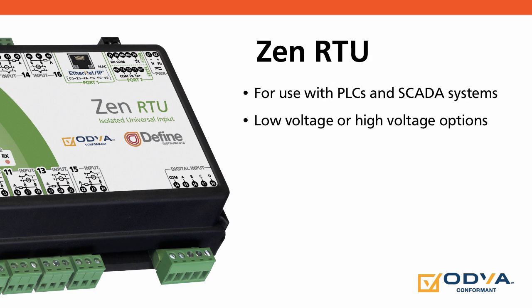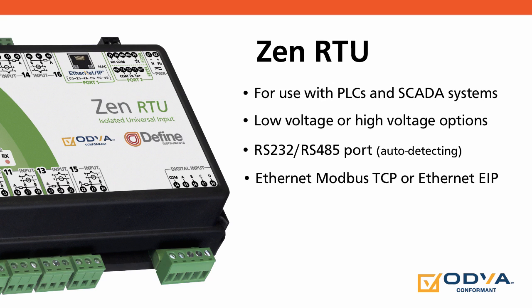It also comes with a standard RS232 or RS485 port, which auto detects which it's connected to. And as you can see, it is also available with an Ethernet port. This comes in either an Ethernet Modbus TCP port, or else it's available with an Ethernet EIP port. And again, you have to specify this when ordering the product.